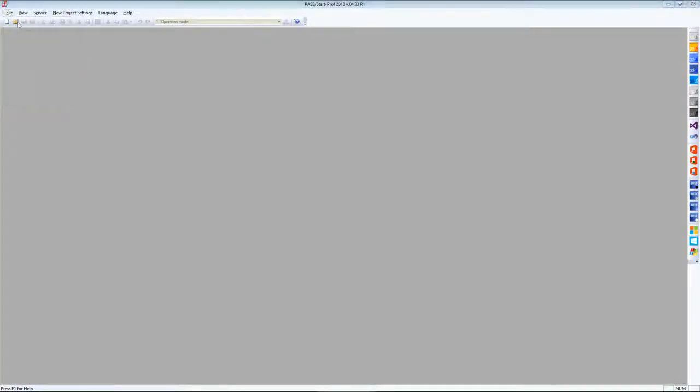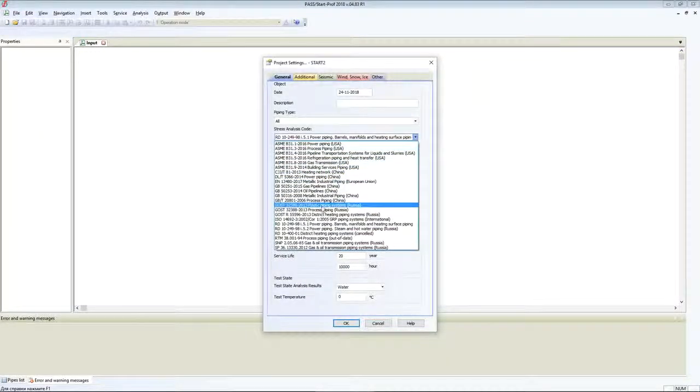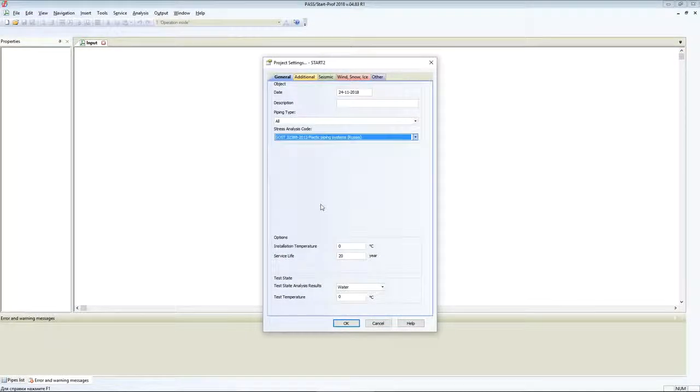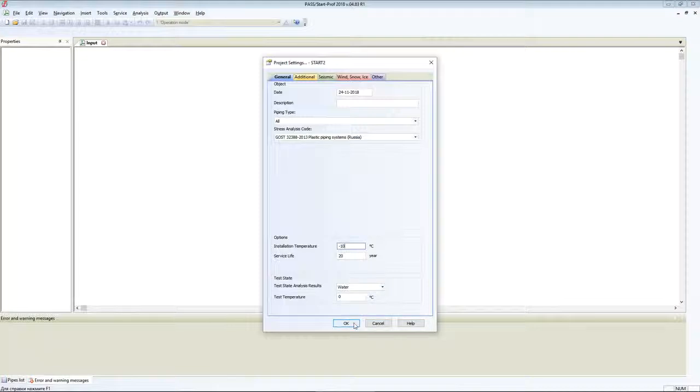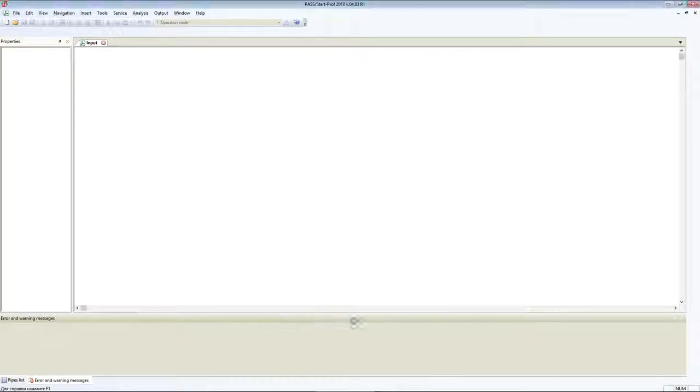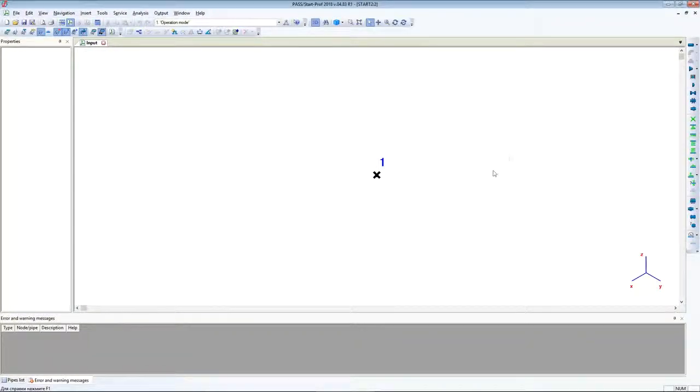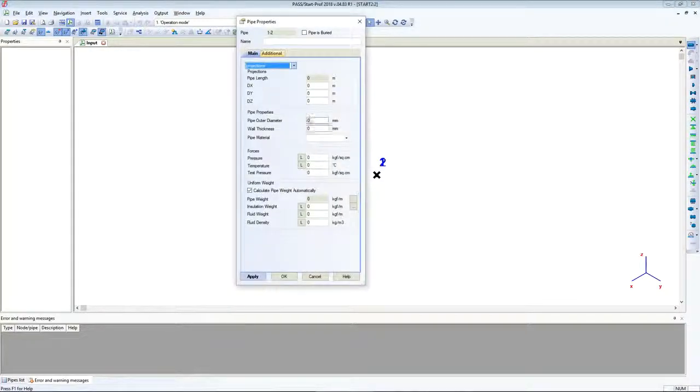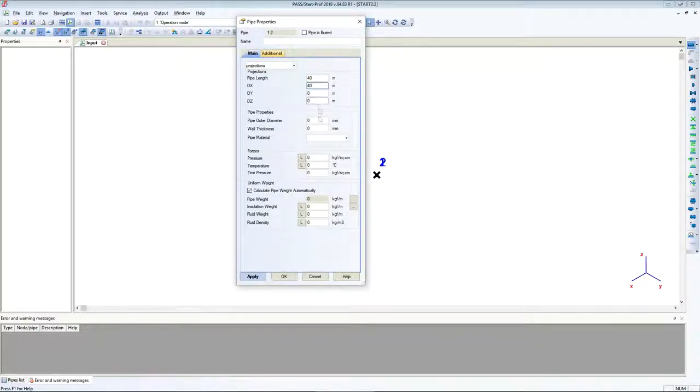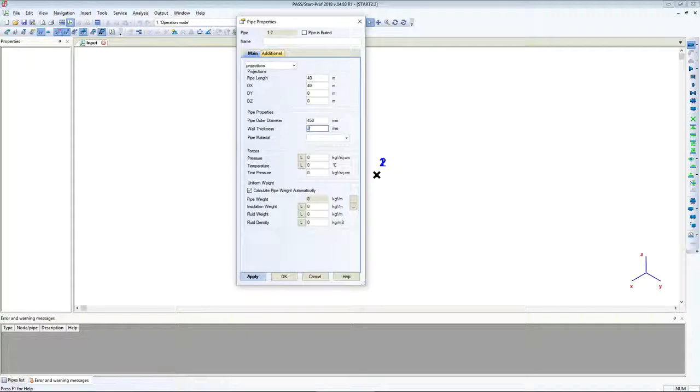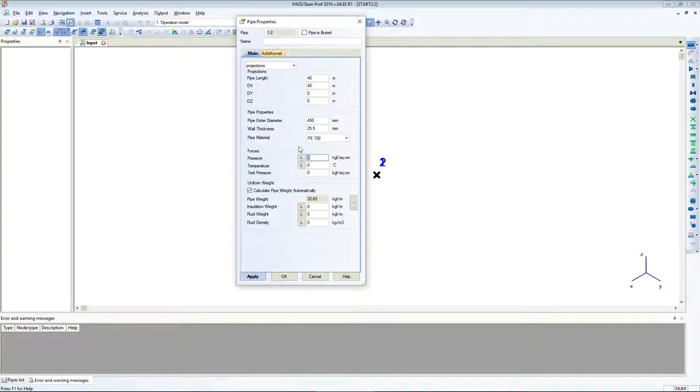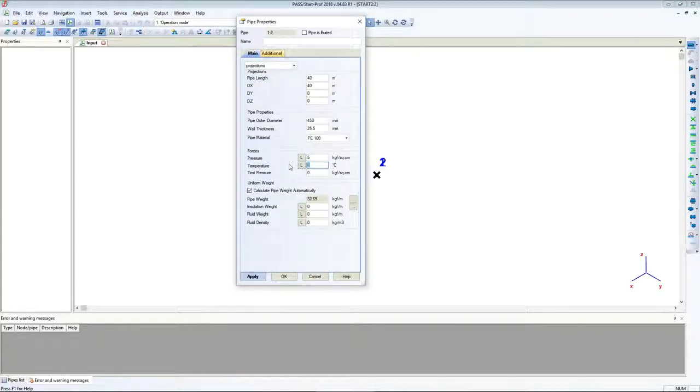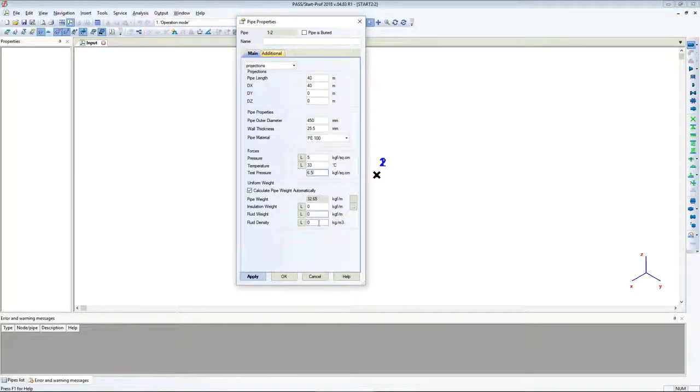Let's create the first file. Select the code for plastic piping systems. Installation temperature will be minus 10 degrees, test temperature 20 degrees. Let's create the first pipe with a length of 40 meters. Set the outside diameter and wall thickness. Piping material will be PE 100. Pressure 5 atm, temperature 23 degrees, test pressure 6.5 atm, and add fluid density.